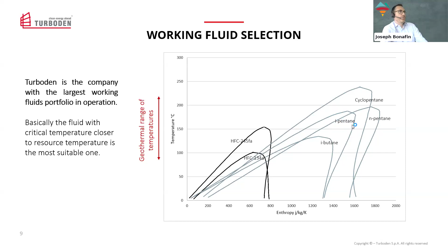Turboden is the company with the largest portfolio of working fluids. In this chart, you see temperature versus entropy with saturation curves. Basically, the critical point of these molecules, which are low boiling working fluids, always falls within the typical geothermal range of wellhead temperature, from 100 degrees up to 250. So it's just a matter of selecting the molecule that has the closest critical point temperature to the wellhead temperature, because that way the thermodynamic process will be greatly optimized.